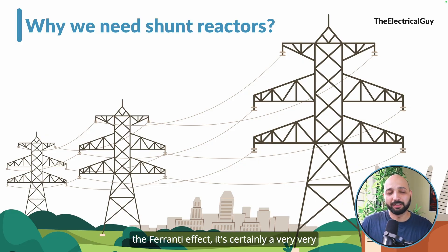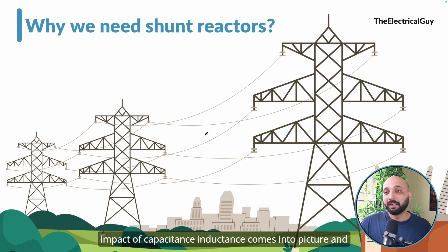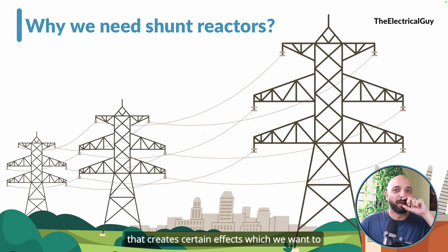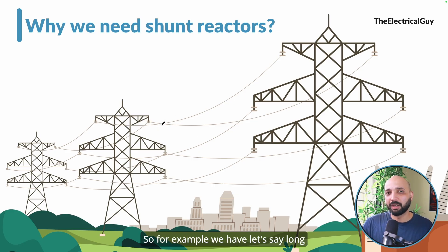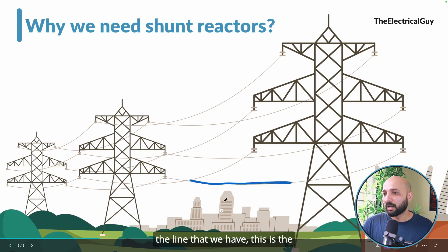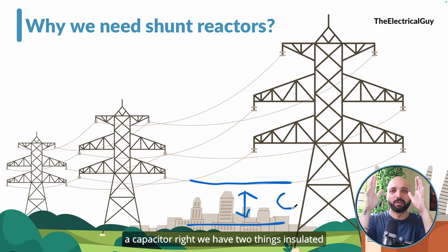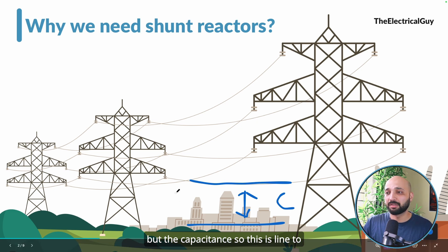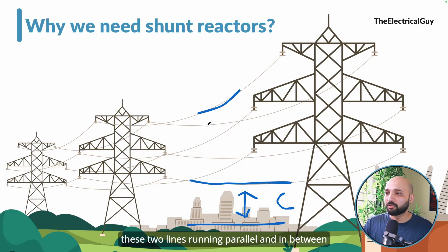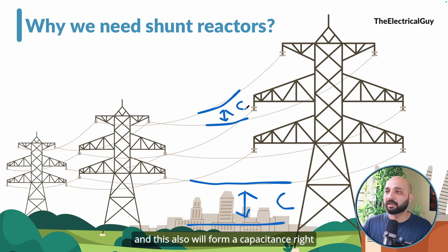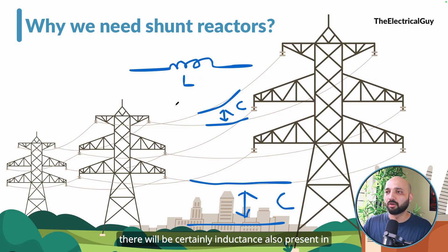In the previous video we discussed the Ferranti effect — a very interesting effect. Generally in long distance transmission lines, 200 kilometers and above, the impact of capacitance and inductance comes into picture and creates certain effects we want to avoid. We have a live line carrying current and at the bottom we have the ground — this is nothing but a capacitor, two conductors insulated by an insulating medium. This is line-to-ground capacitance. We also have two lines running parallel with air as insulation between them, which also forms a capacitance. Similarly, this transmission line carries alternating current, so there will certainly be inductance present in the line as well.